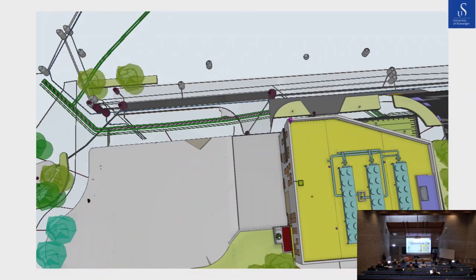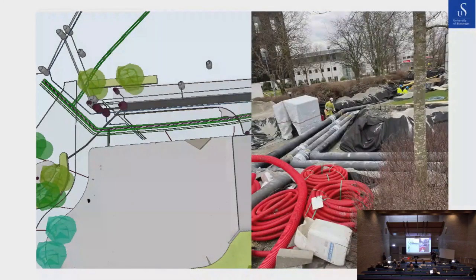And again, just to see the spaghetti in the ground there, you need a lot of piping. So that's also one of the important points of the semi-deep concept, that you can reduce a lot of this piping, ditch work, etc. Exactly. So had they been successful, we would have had a very nice paper. Now we hope to describe what went wrong, try to set up cost calculations and do this comparison: if the whole system had been established with semi-deep boreholes instead of 300 meters, how much would you have saved on the piping, etc. Which I think is the final slide.